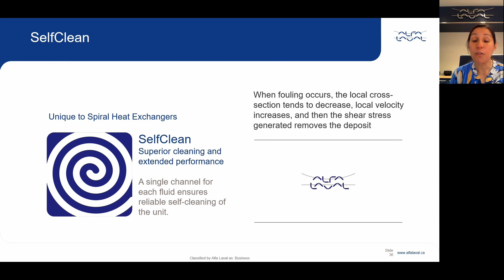And this is very unique to the spiral because the spiral is the only product that has a single channel configuration, compared to Compablocs or shell and tube, where you have multiple flow channels through the heat exchanger. The spiral heat exchanger construction is a single channel, so it provides the ability to supply this self-cleaning effect.